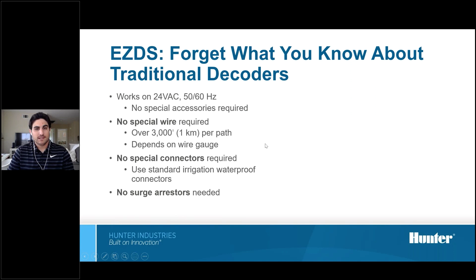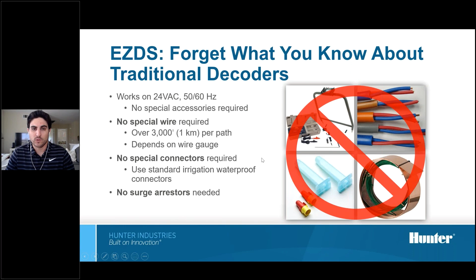Lastly, there are no surge arresters needed in the 2-wire path. So ultimately, all these high spec items that you saw on the previous slide kind of go out the window with this system. Big time saver, big cost saver, big labor saver, not having to use all these high cost items that we talked about previously. So that's pretty much in a nutshell how the EZDecoder system came to light and how it operates. 24 volts, can use a variety of wire available, can use a variety of wire connectors available, and then hey, you don't have to ground the 2-wire path. We recommend you ground the controller because that's the most important piece to the puzzle, sending out signals to all your decoders in the field, but you don't need to pay for those extra grounding rods or ground plates on that 2-wire path. That's money back in your pocket.